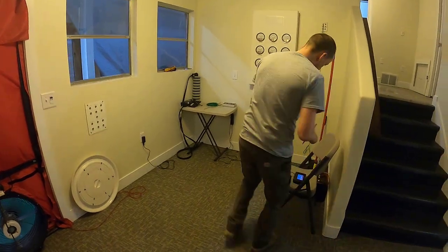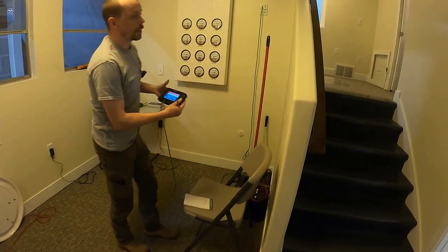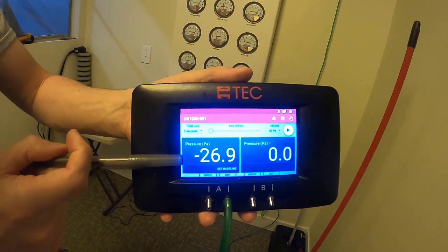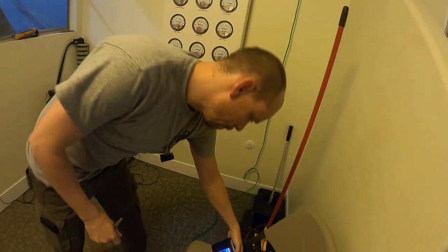Then I've got to go look at my zonal again into my attic, and I'll record that zonal pressure of negative 26.9.